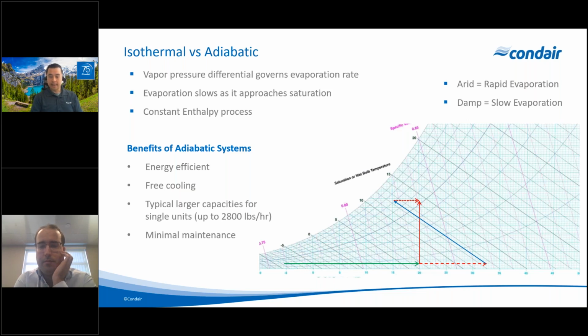Looking at this on a psychrometric chart, for an isothermal process or steam system, we assume there's no temperature change between the entering and leaving air after humidification. That's the red line—effectively following the temperature straight up while increasing humidity within the space.